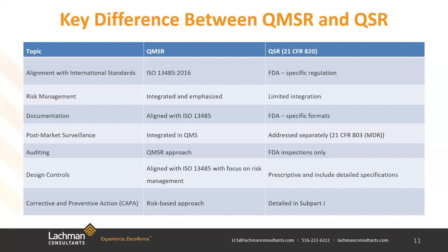Now we move to design controls. For QMSR, alignment with ISO 13485 requirements, but harmonized to maintain FDA's critical design oversight with a focus on risk management during the design phase, whereas QSR design control requirements are more prescriptive and include detailed specifications for procedures, reviews, and validation. Corrective and preventive actions: for QMSR, they are addressed under ISO 13485 as a part of a broader quality management system, and they emphasize root cause analysis and risk-based prioritization, whereas the QSR defines CAPA requirements in more specific terms under subpart J of part 820, focusing heavily on documentation and reporting.